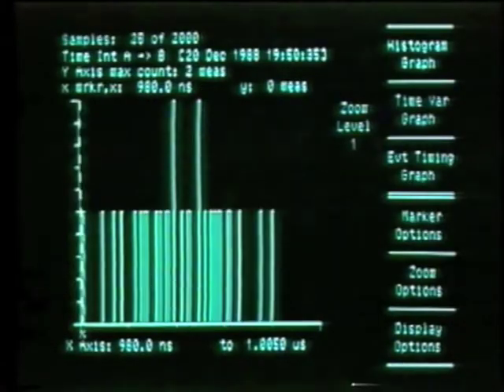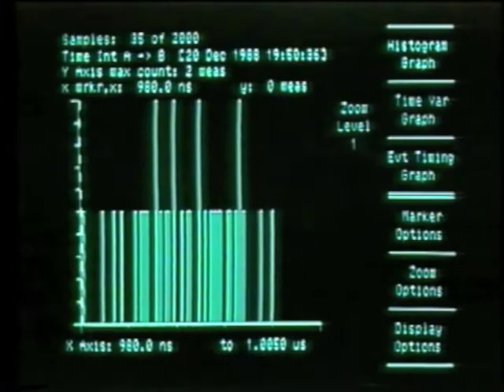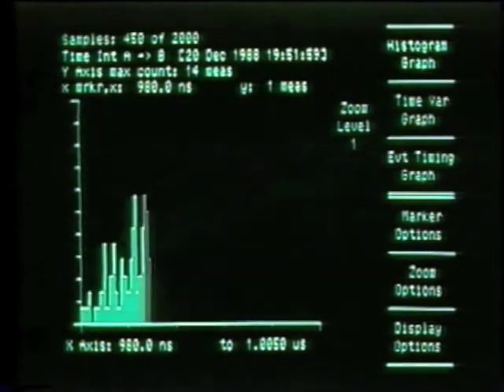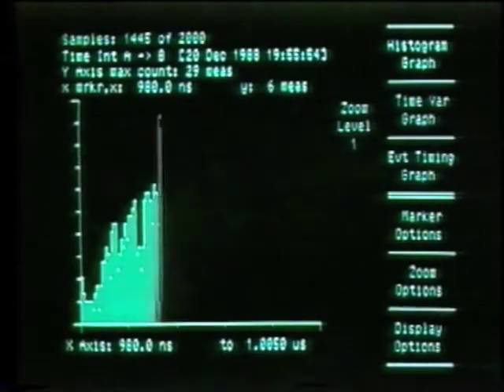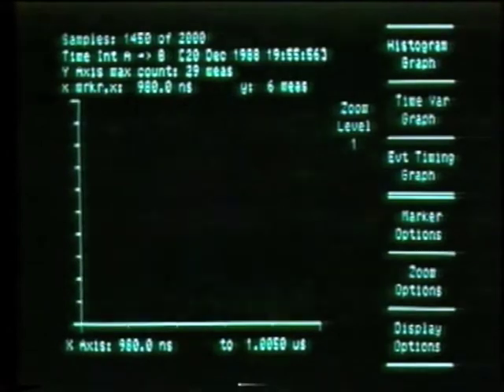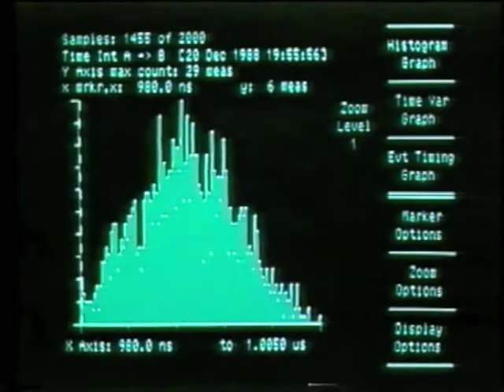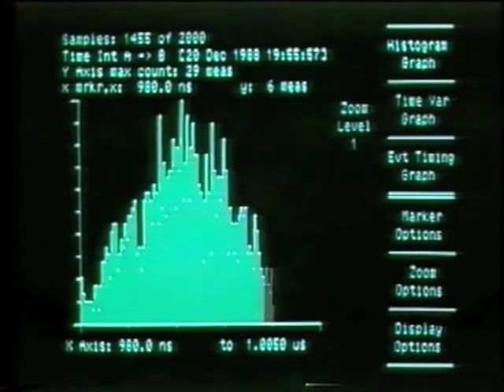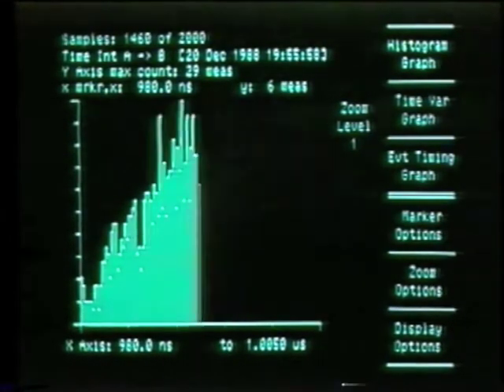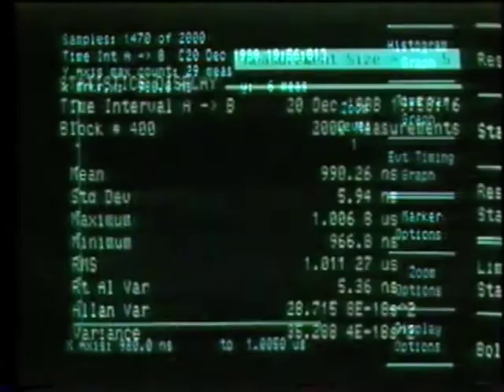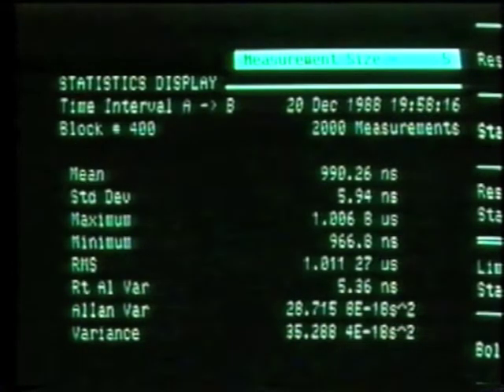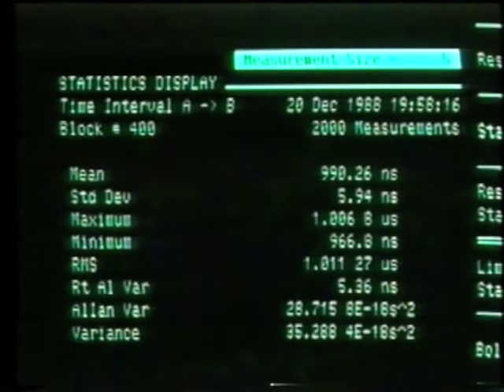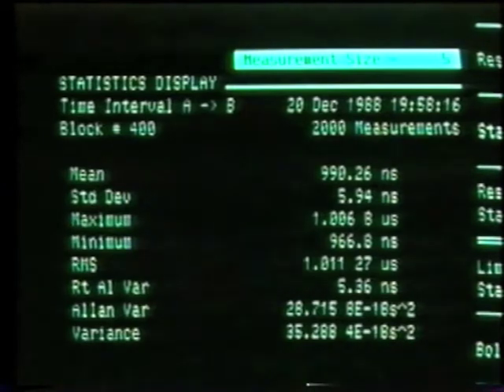A histogram graph shows how the results are distributed, and we can even see the histogram growing as the instrument acquires more and more data. The 5371 also gives us a statistical summary, computing the mean, maximum, minimum, and standard deviation.